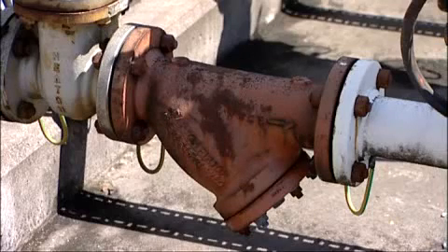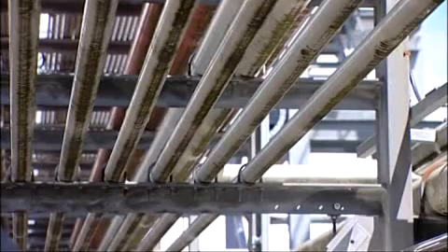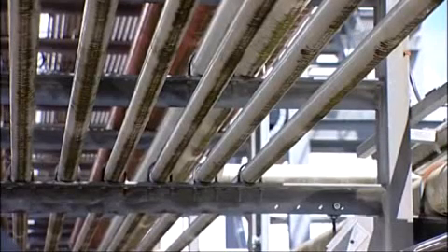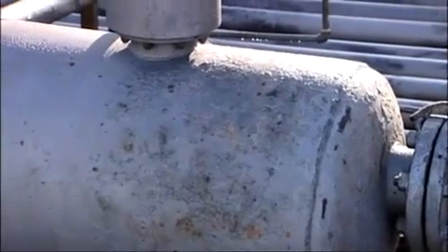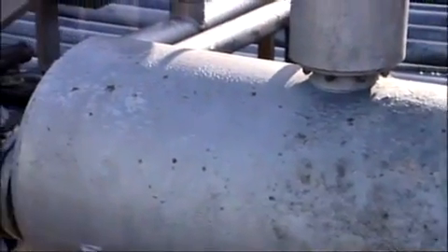Experience has shown that installing filters far enough upstream of discharge points to provide a sufficient liquid residence time greater than the specified charge relaxation time of the liquid will avoid problems. This can also be achieved by the installation of a relaxation chamber.